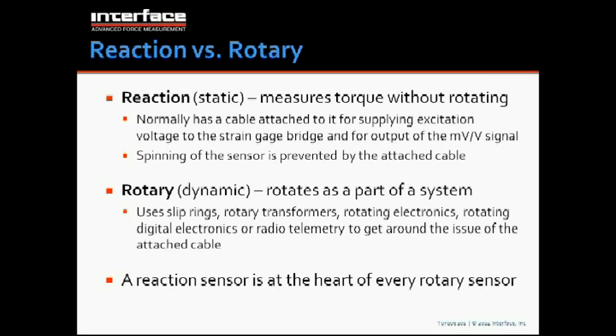We have two different types of torque sensors we talk about commonly, reaction and rotary. That's sometimes confusing to people. Obviously, rotary ones spin, reaction ones don't, but what is the real difference between the two? So to start off, we're talking about a reaction sensor, and that's a sensor that has a strain gauge sensor, like we said, that measures torque. Typically, though, to get the signal off of the strain gauge area and to apply the power to the strain gauge bridge, we have to have a cable attached.